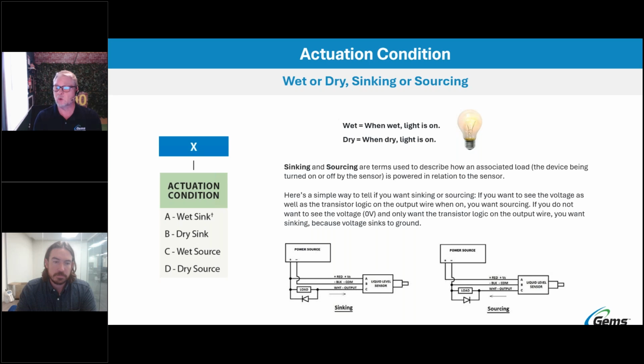If you're not familiar, sinking or sourcing is basically how it's wired in your circuit—terms used to describe how the load, what you're trying to power, relates to the sensor. A simple way to tell: if you want to see the voltage and the transistor logic, the yes or no, the ones or zeros, on the output wire, then you want sourcing. If you don't want to see any voltage and just want that yes or no logic on the output wire, you want sinking, because that voltage then sinks to ground, or in this case, the negative leg of the DC power source.